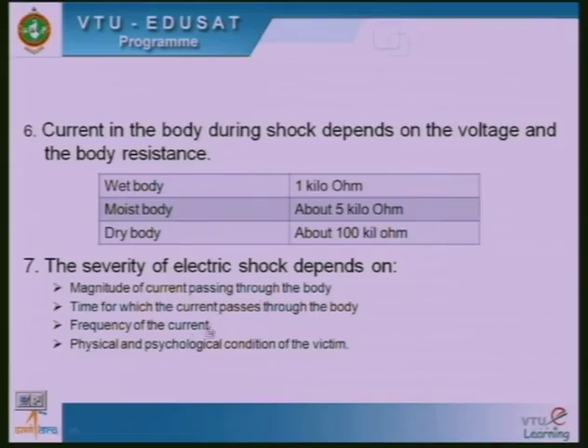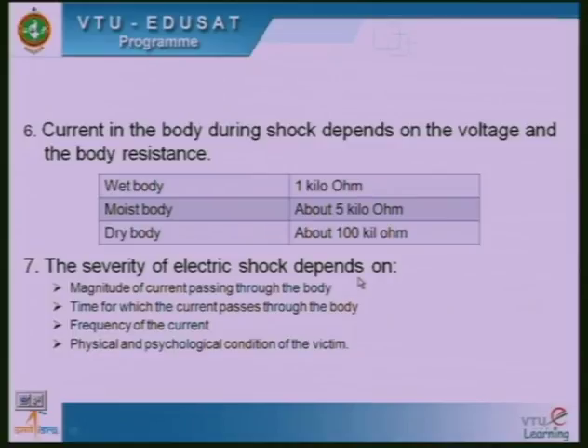The severity of the shock depends on the magnitude of the current passing through the body and the time for which the current passes through the body. Even if the current is minimum, but it flows for a long time, okay, then also there will be an effect. The frequency of the current also has an important effect on the shock. Then the physical and psychological condition of the victim is also very important. So, all these 4 points affect the severity of the shock.